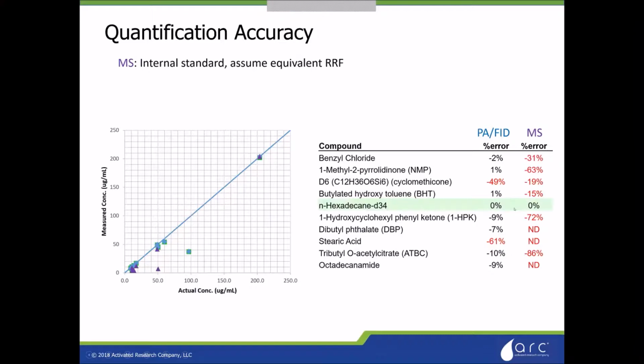So this is with an internal standard, assuming an equivalent relative response factor, just like we did with the polyarc FID. You can improve this, and a lot of people in the extractables and leachables business will use either surrogate molecules or a lookup table with response factors. In this case, we use surrogate molecules with 5-point calibration curves, and the errors actually got worse. So obviously, it depends heavily on which surrogate molecules you choose, and with a mass spec, it's very hard to target what's going to have the same ionization cross-section to pick a surrogate molecule.